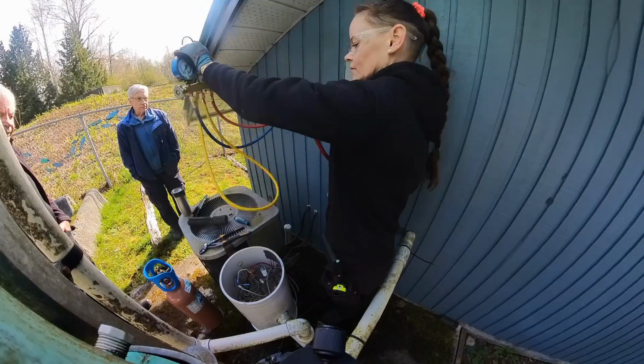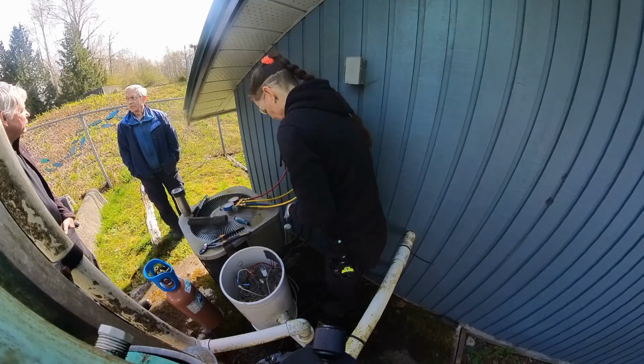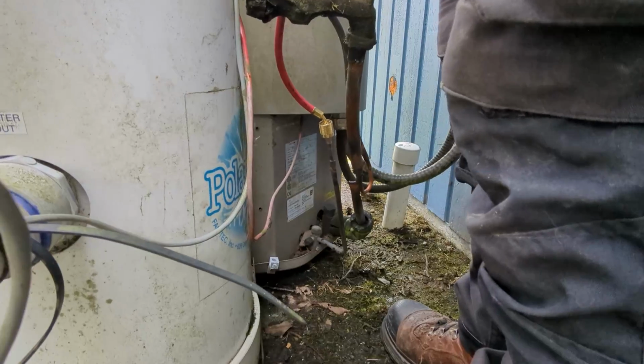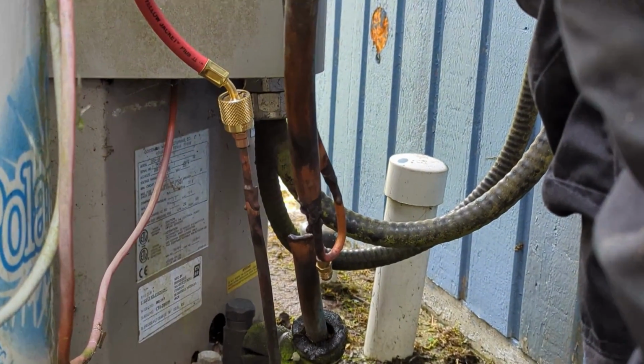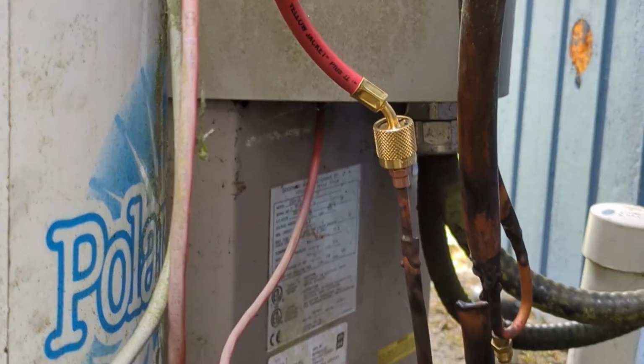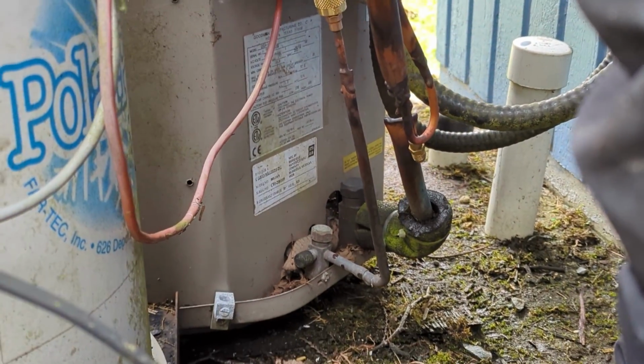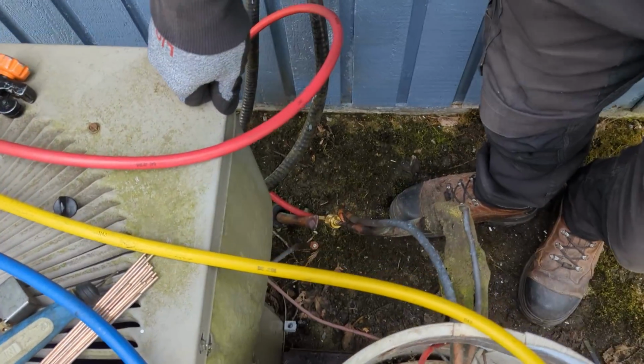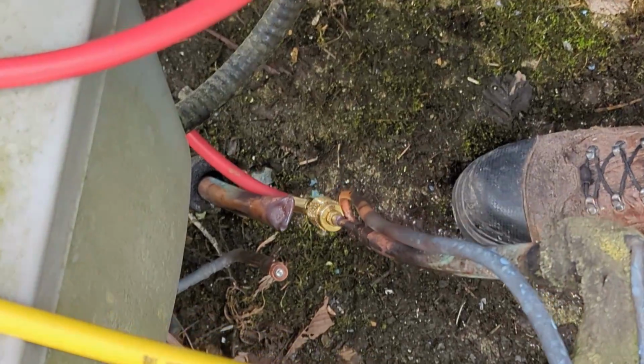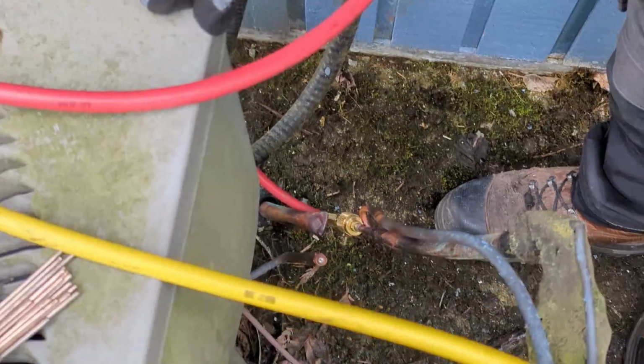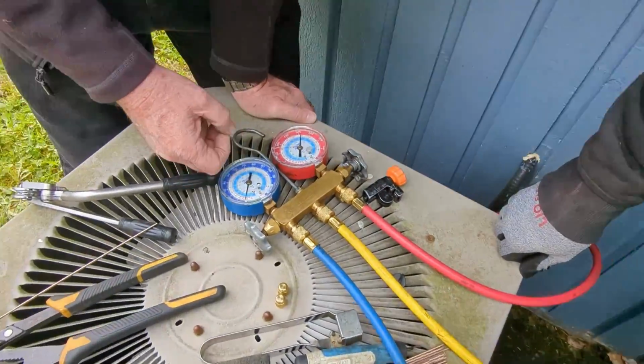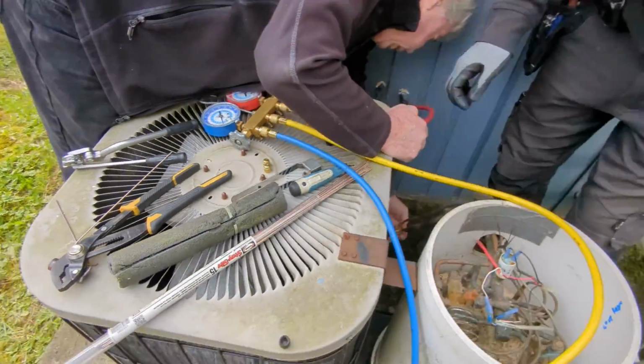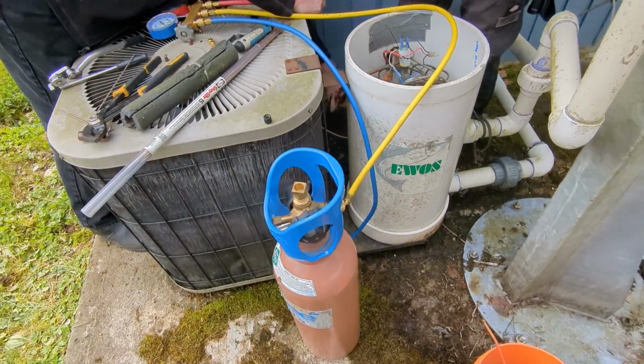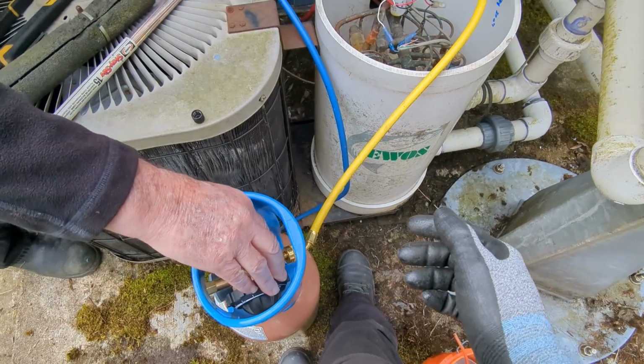Now those access fittings are welded in. We're going to bump up the pressure with nitrogen on both sides, up to about 300 pounds. You can see those access fittings Trev brazed in for us. The plan is to leave both sides pressurized over the weekend, and we'll come back next week to check whether it's dropped, and whether it's one of the components or both.